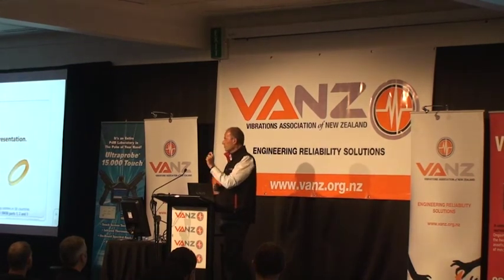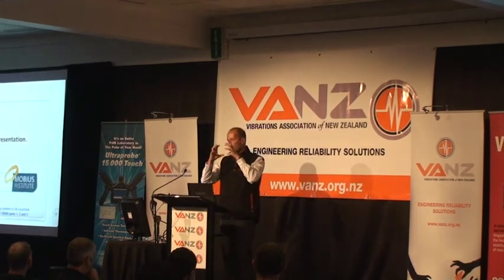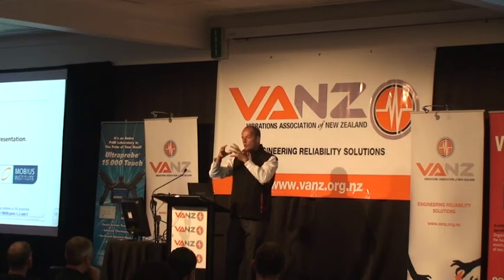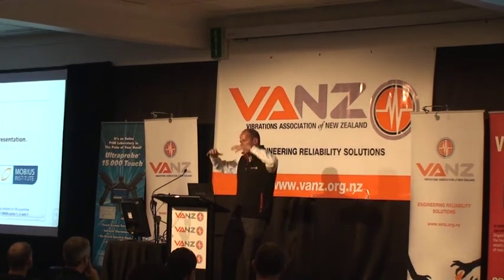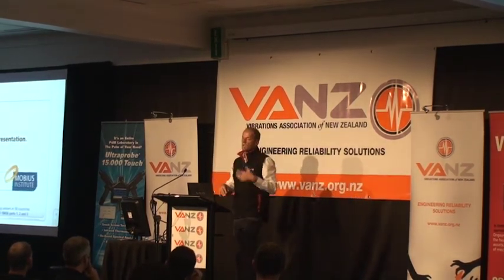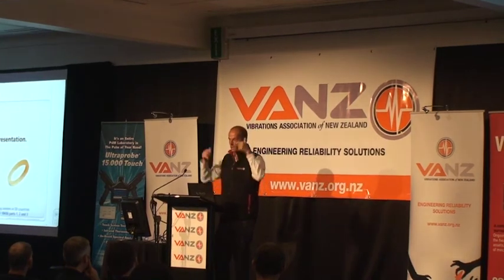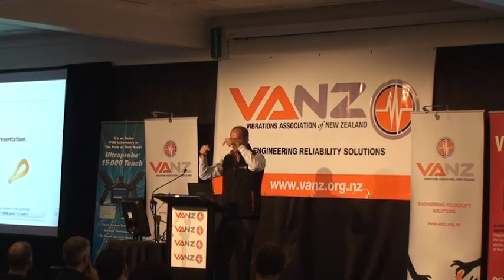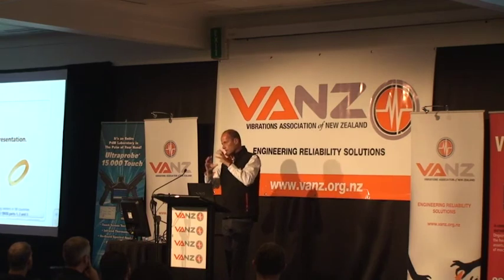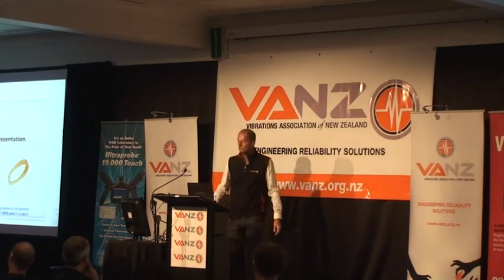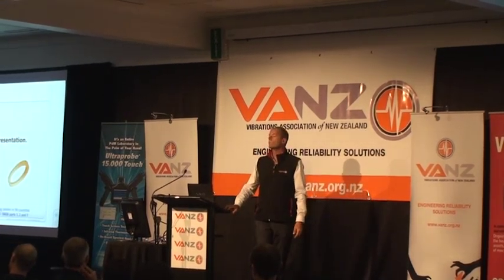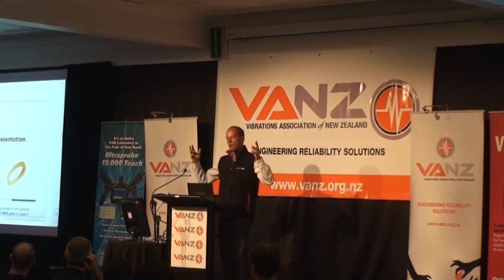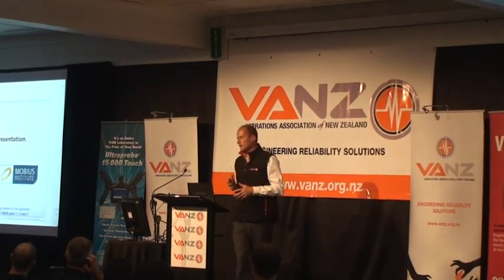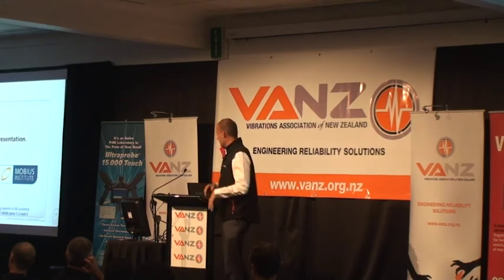The other issue is that the transmission of the vibration, or the motion, through that oil wedge to the bearing, to the housing where you're taking those measurements, there's a lot of damping that goes on. And that's another reason why we want to take that measurement, to really see what's happening. One more question. As I say, we just summarised a whole Cat 4 course in the last 30 minutes, so that's why I had to generalise on a few things.